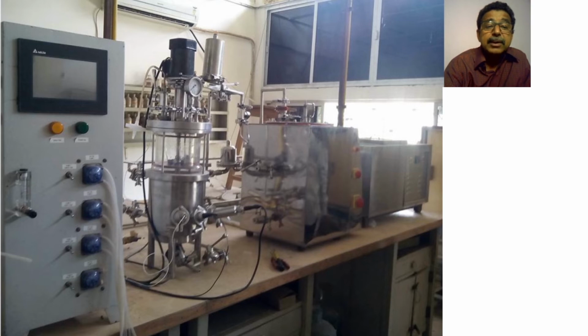So in this pump, what happens? The tubes are connected to the vessel, where one pump is connected with acid, sterilized acid. The other pump is connected with sterilized alkali. So acid and alkali. Now it is PID control. Whatever data the pH probe gives, on the basis of this, the PID control will decide. Suppose your pH requirement is 6.5. So you set the pH to 6.5. You ask this PID control to keep the pH at 6.5 inside the vessel.